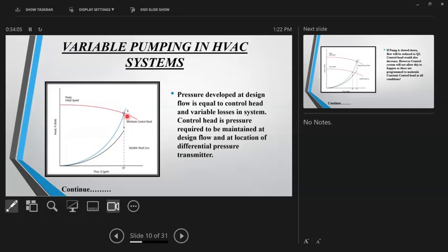Fixed head is what? Let us read. Pressure developed at design flow is equal to control head and variable losses in the system. So I have quietly used the word control head. Two minutes back, I was using a word, which is fixed head or constant head. Suddenly I have changed to control head. So what is this control head?